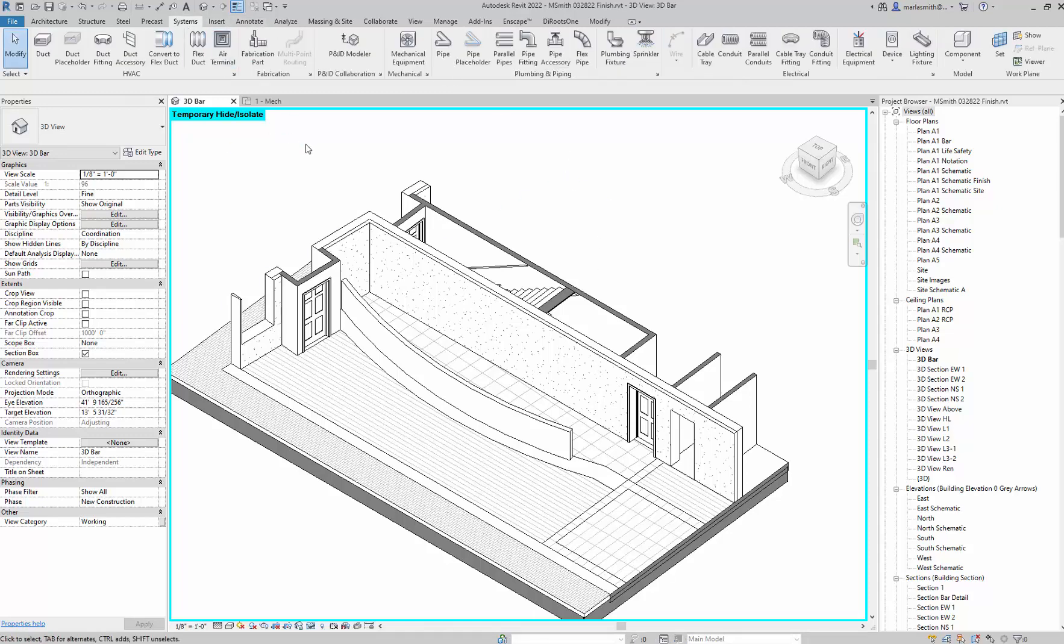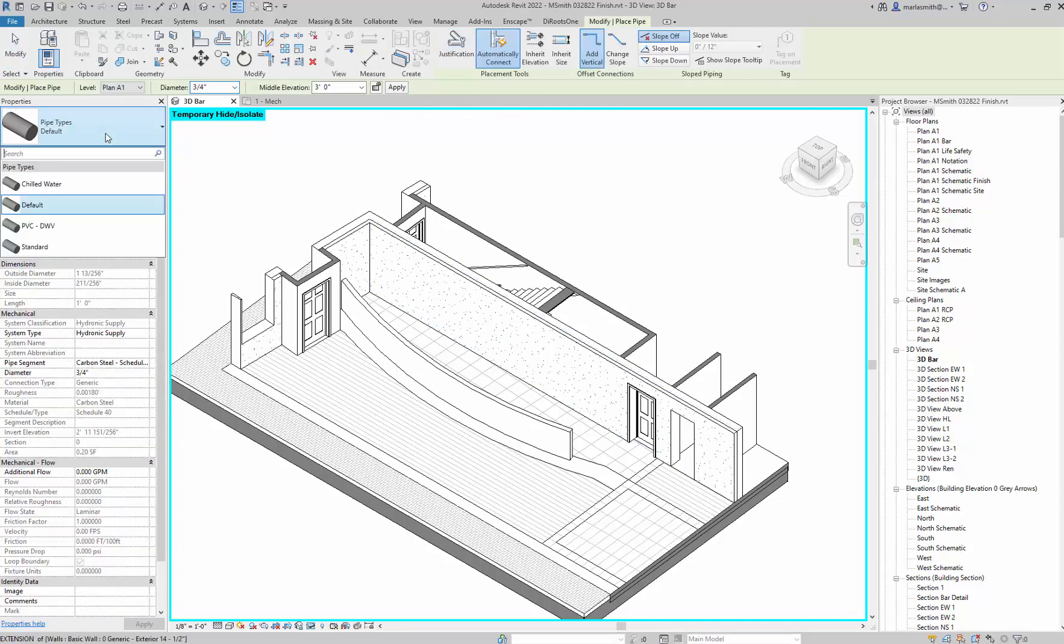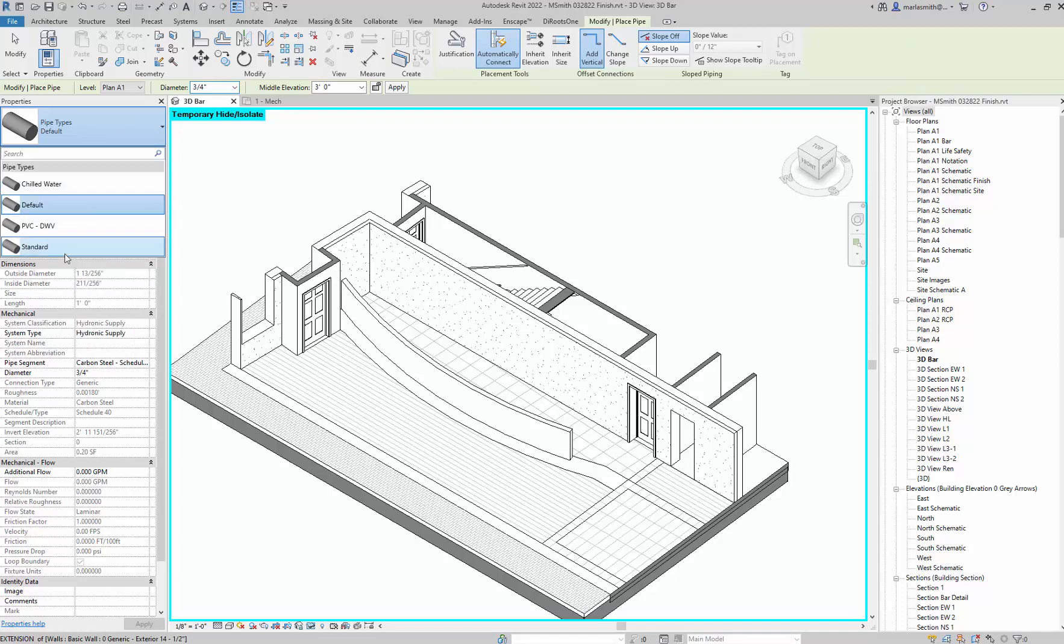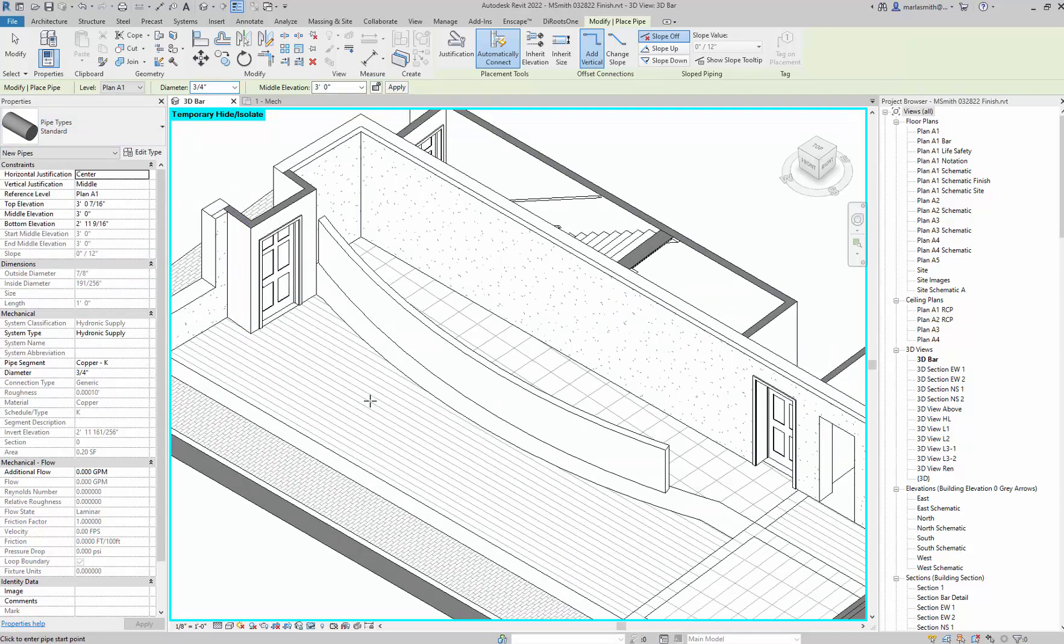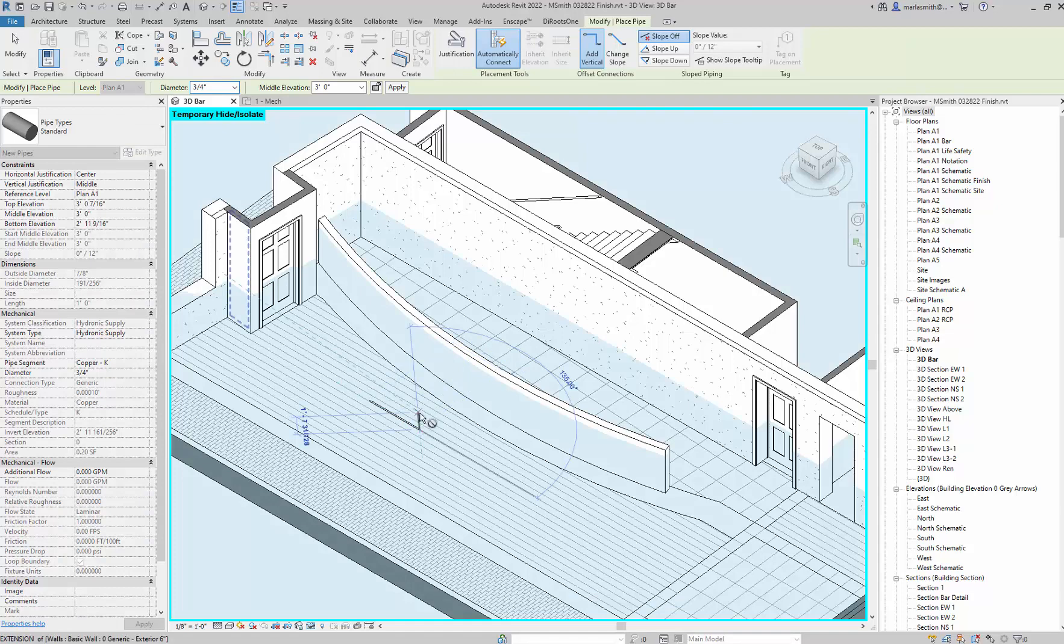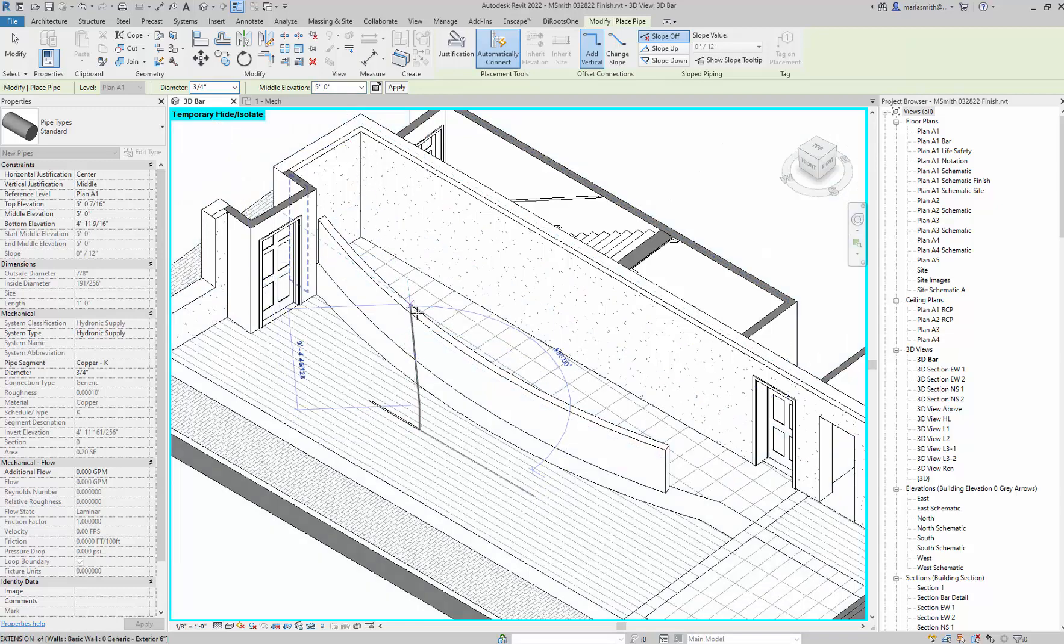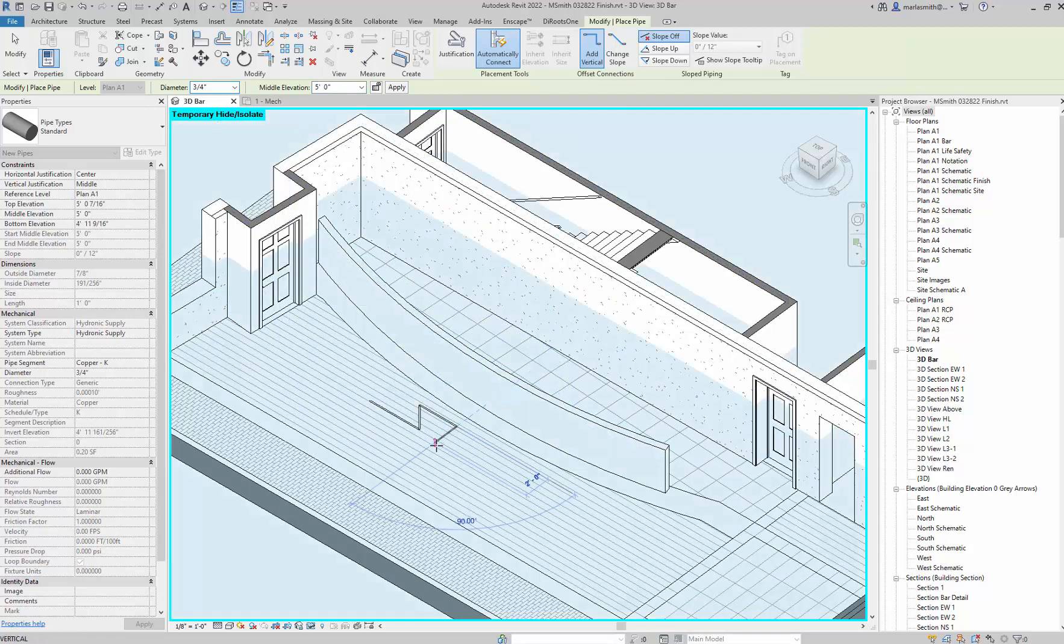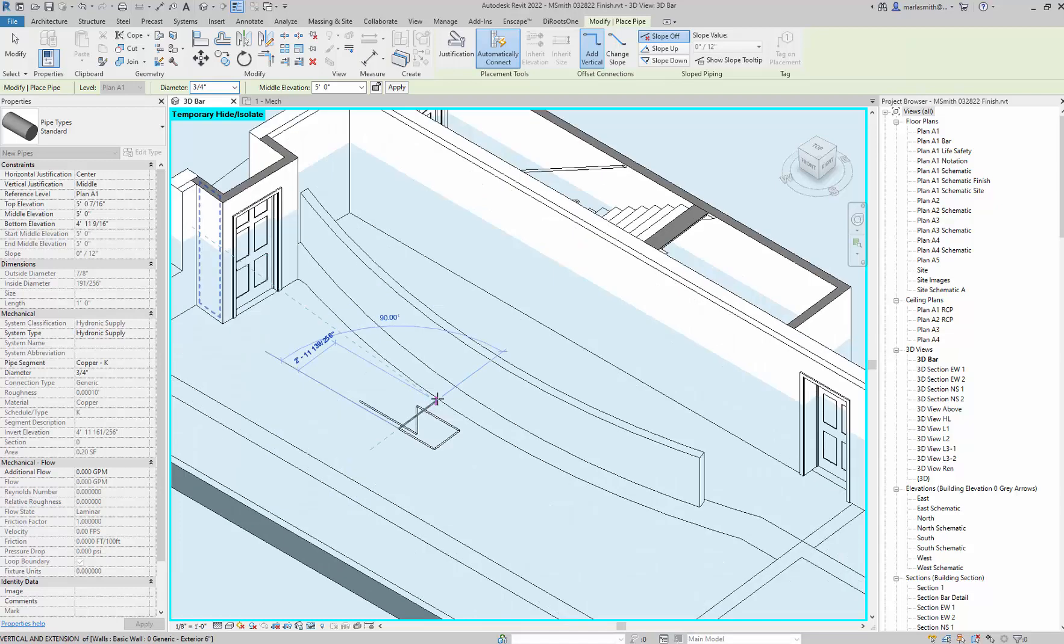Now when I go to systems, I can go to pipe and instead of default, I can pick chilled water, standard, or PVC because it's loaded all those in. I'll go to Standard and set it at three quarters, and now I'm drawing at three feet. Then I'll put it at five feet, and it'll now draw a piping system for me.